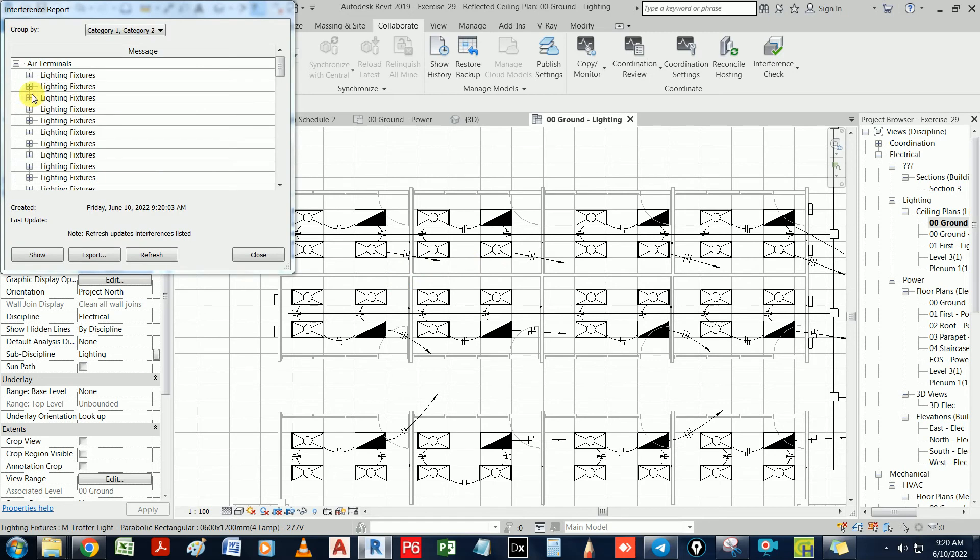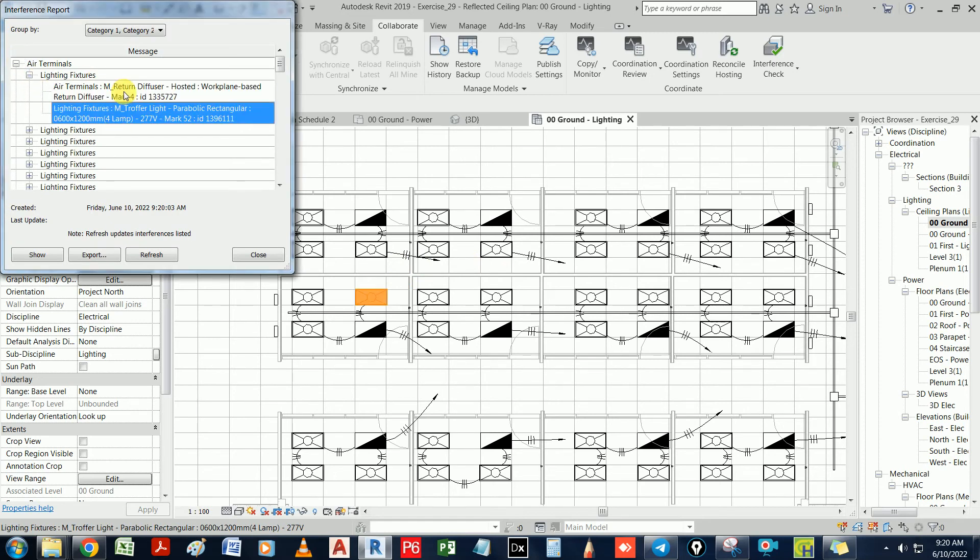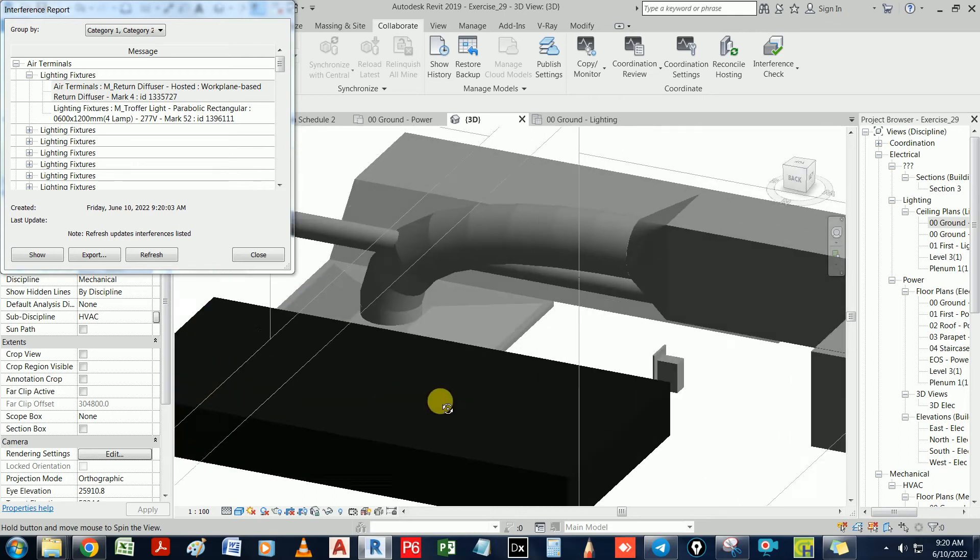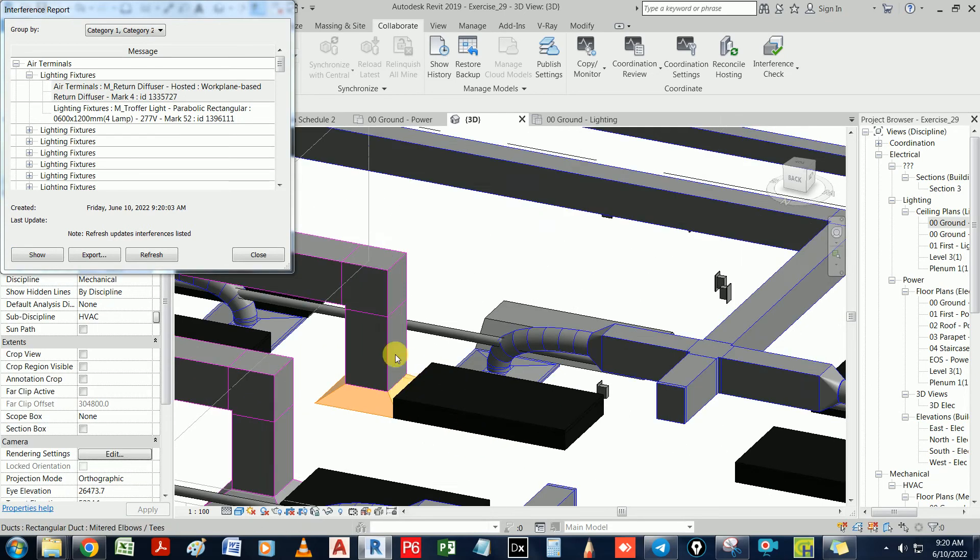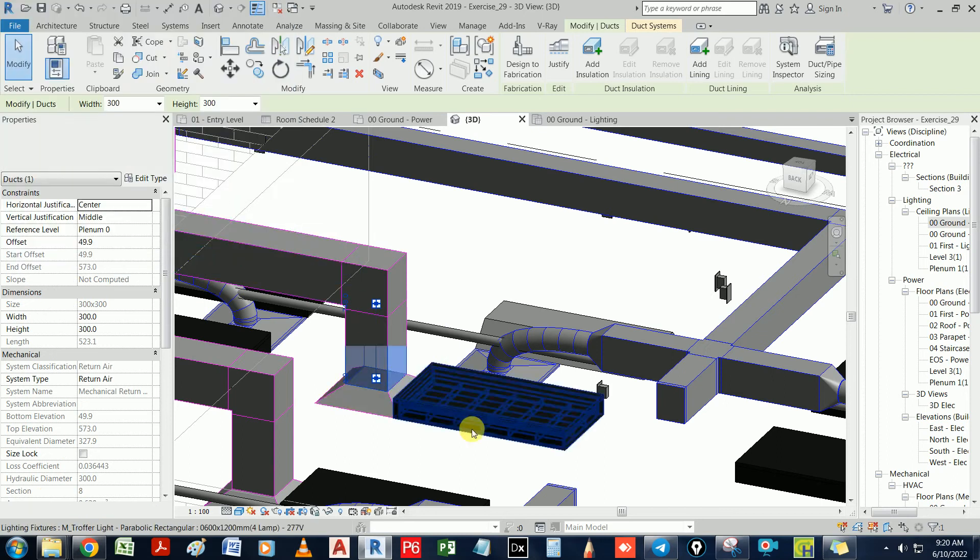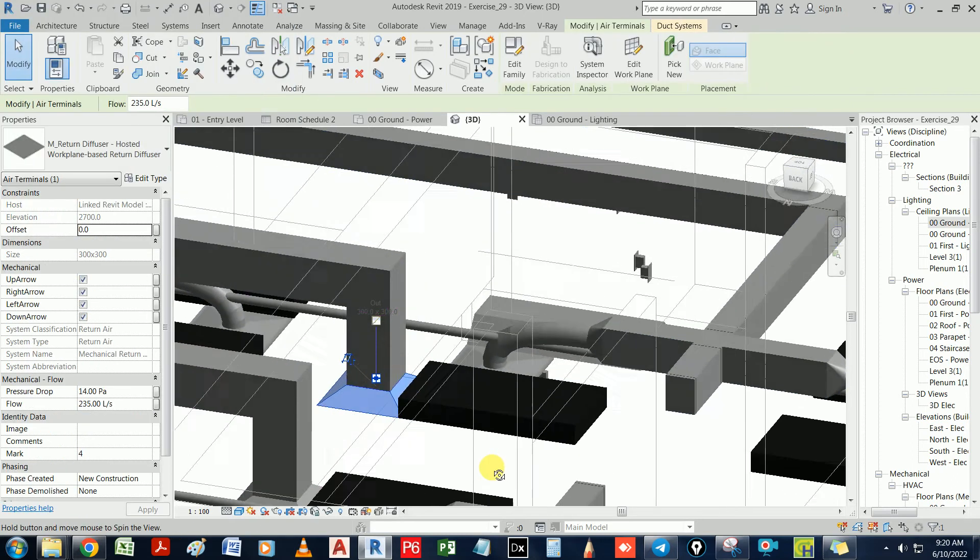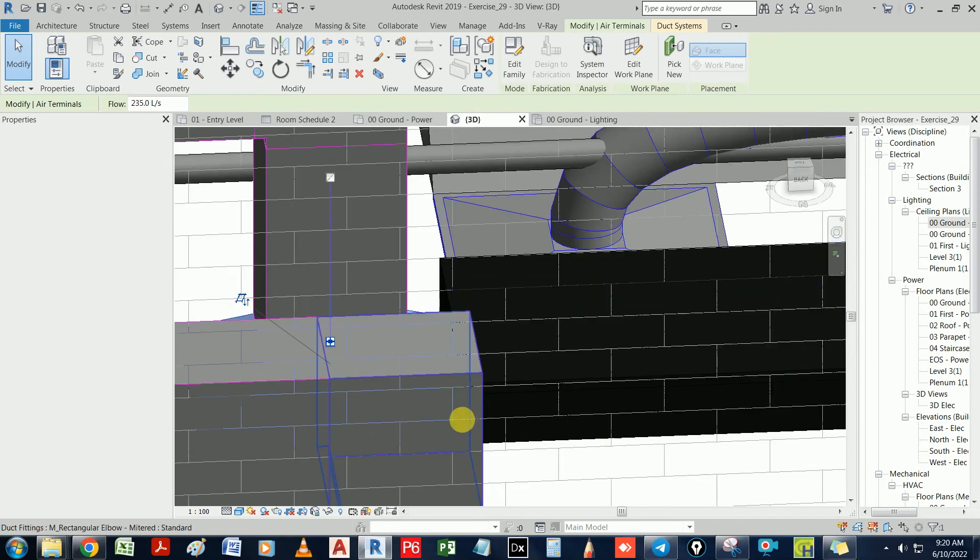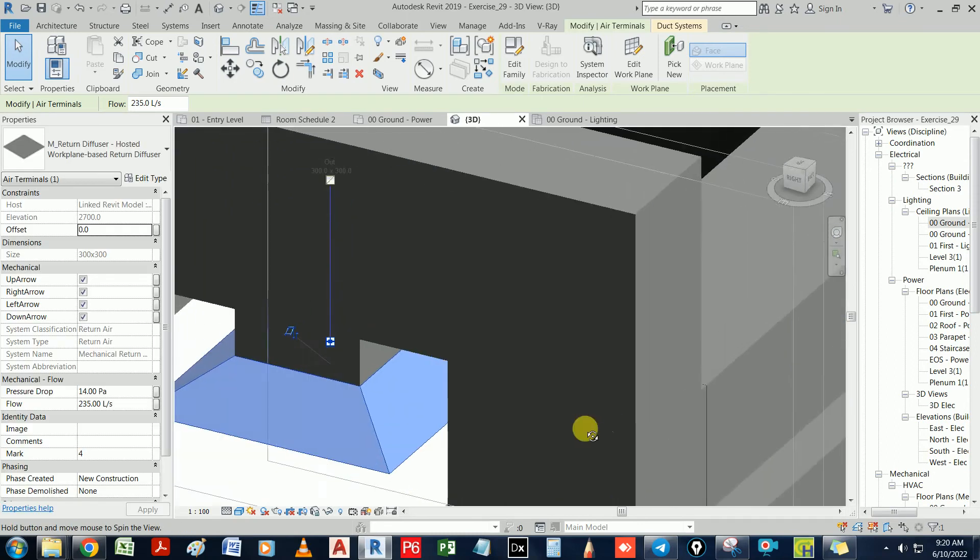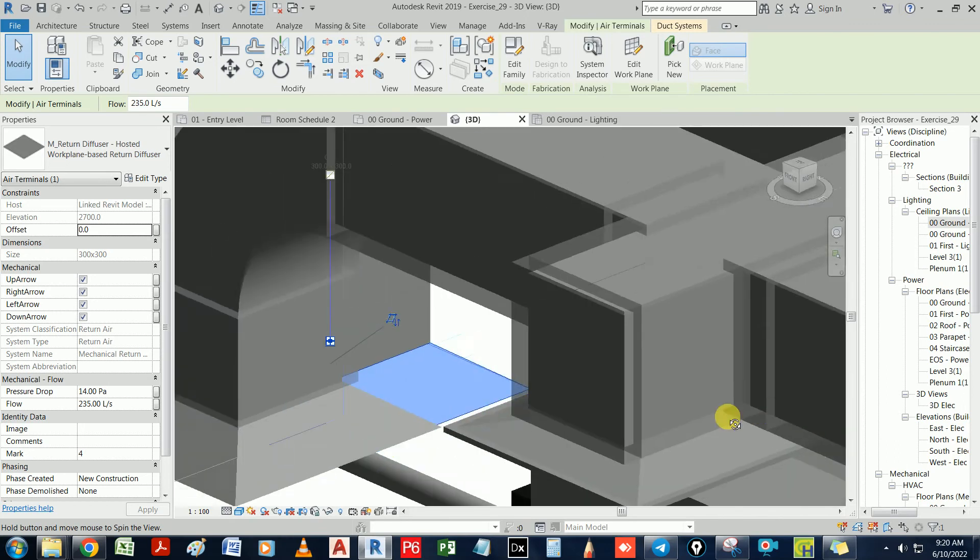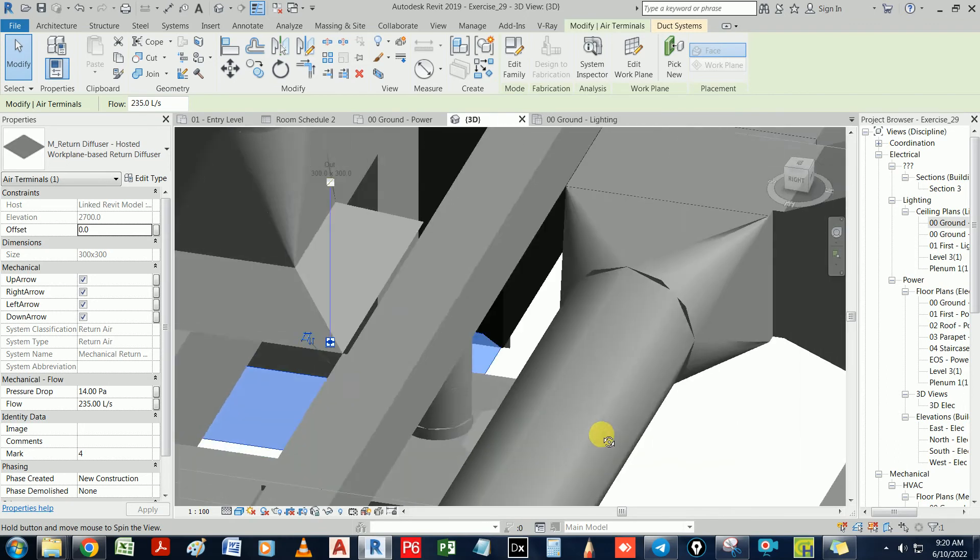See, I said there is a clash with lighting. There is one clear clash. Most probably it is here. There is a touch. Let's show it in a 3D view. See? You get the picture. This is Revit. Revit helps you find interference. See, you can see it, just a small touch. I hope this is clear.